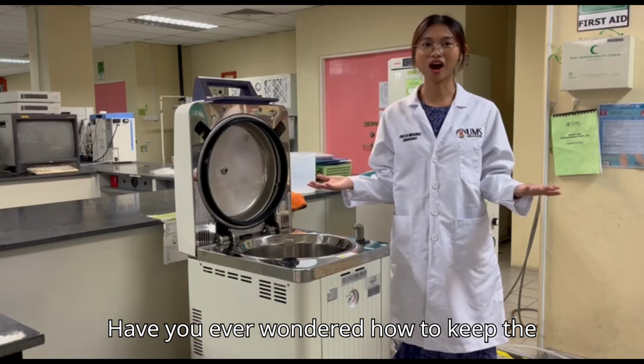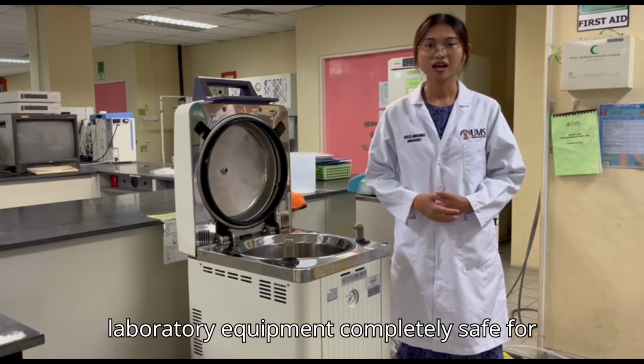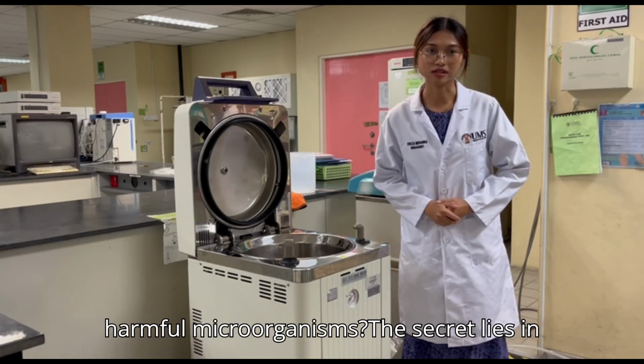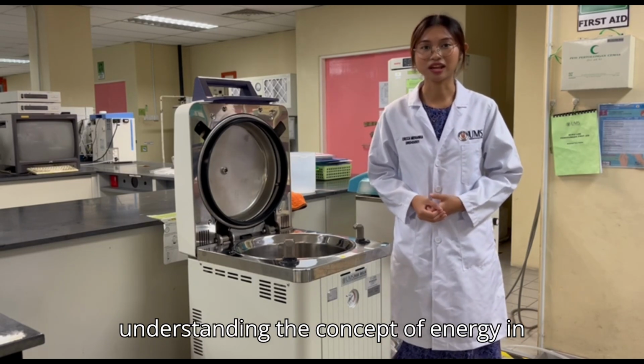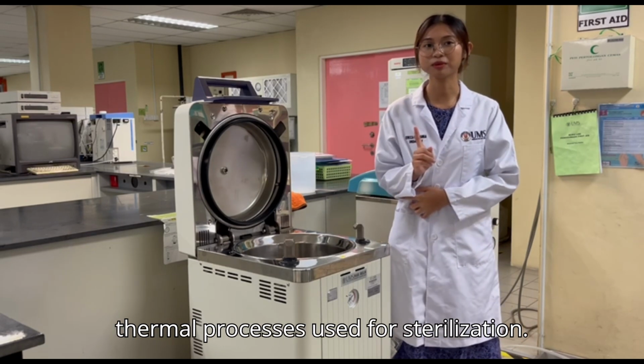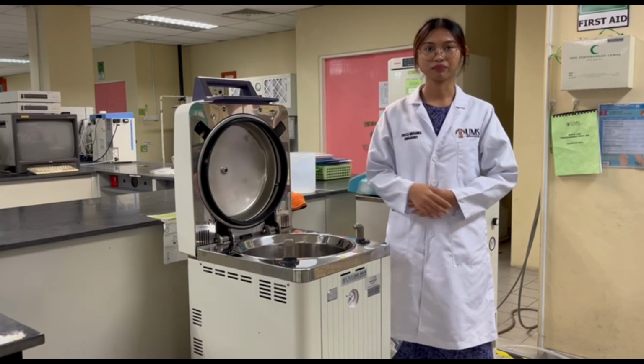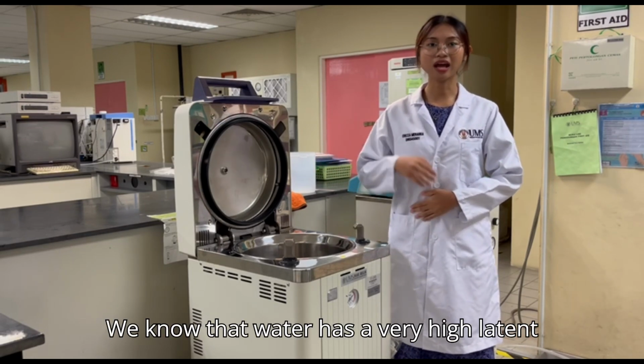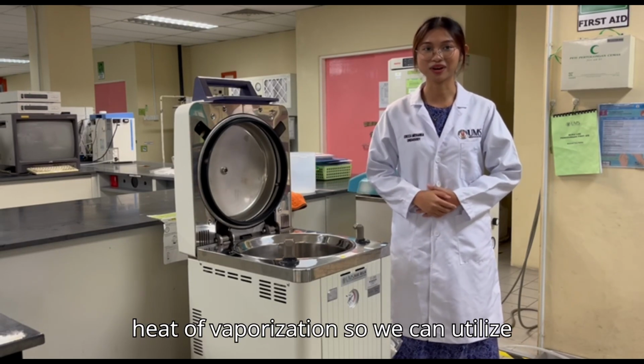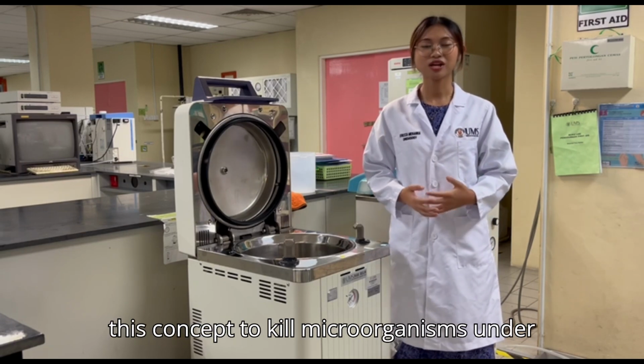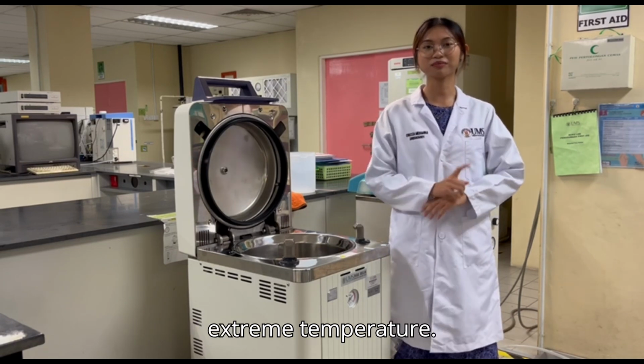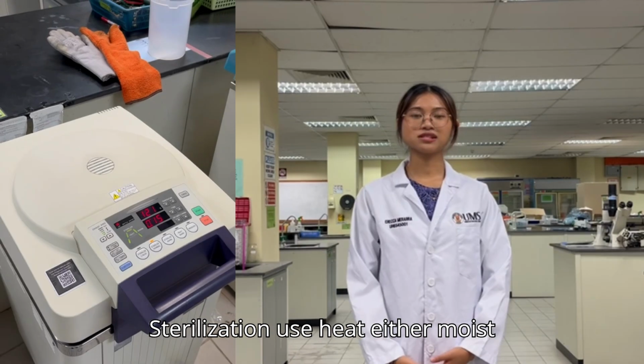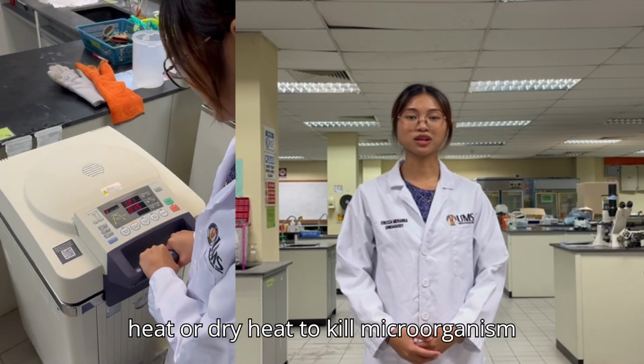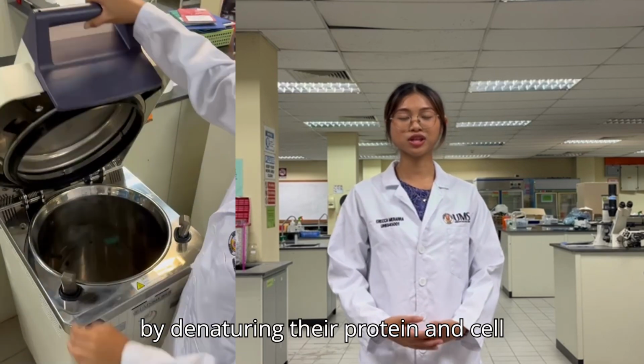Have you ever wondered how to keep the laboratory equipment completely safe from harmful microorganisms? The secret lies in understanding the concept of energy in thermal processes used for sterilization. We know that water has a very high latent heat of vaporization, so we can utilize this concept to kill microorganisms under extreme temperature. Sterilization uses heat, either moist heat or dry heat, to kill microorganisms by denaturing their protein and cell wall.